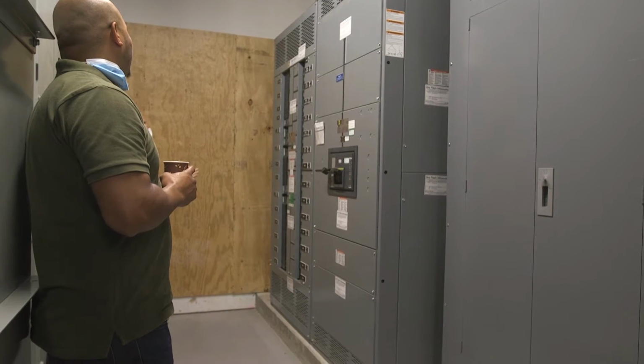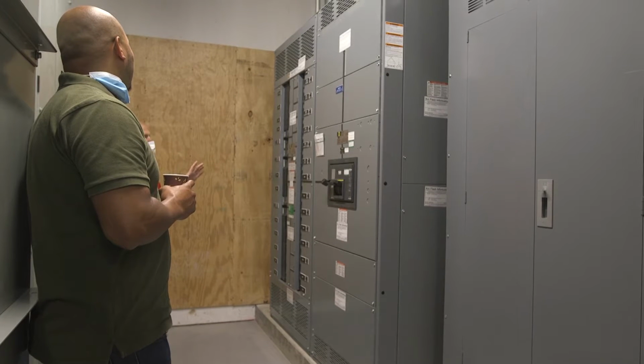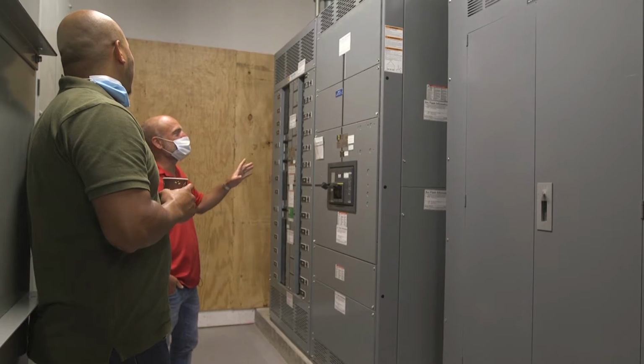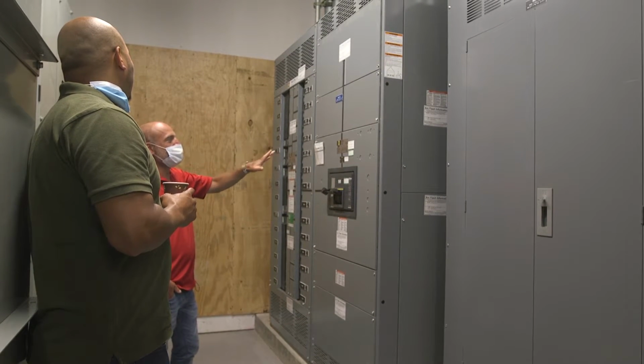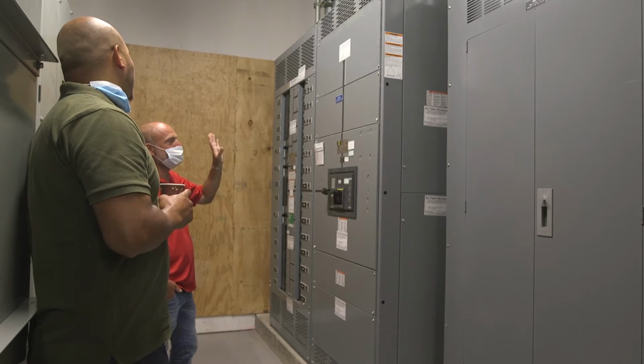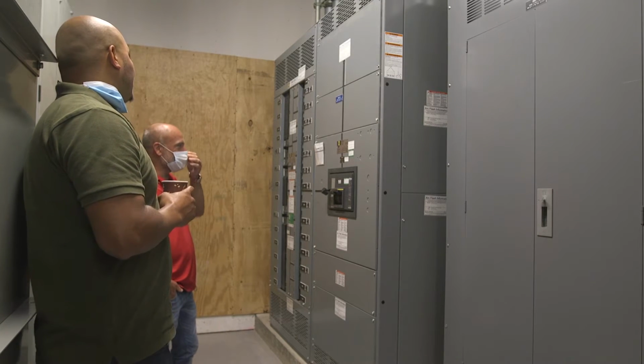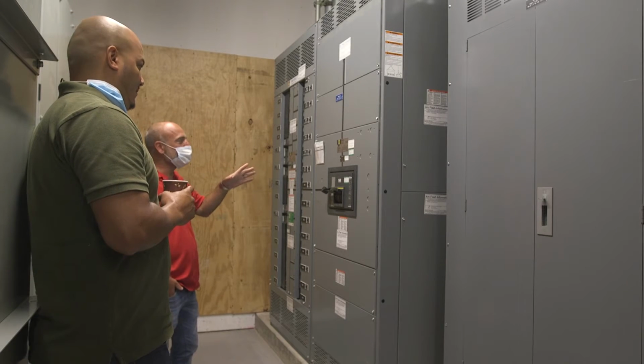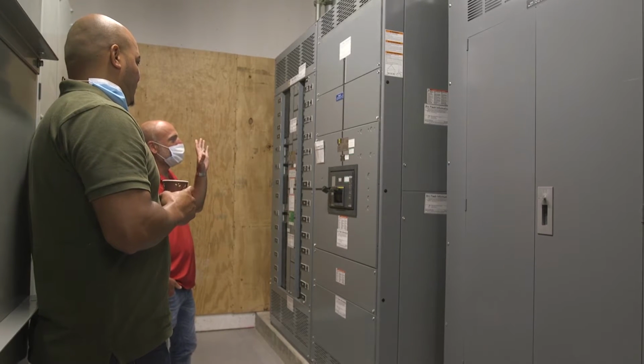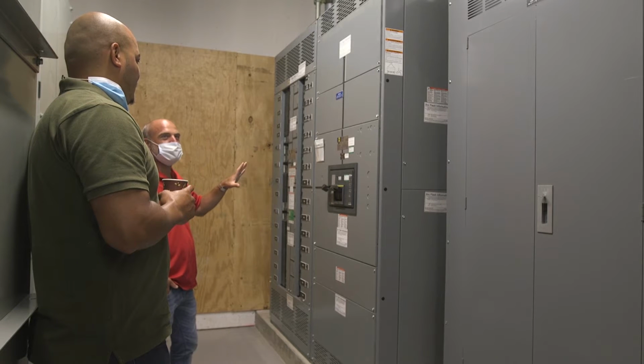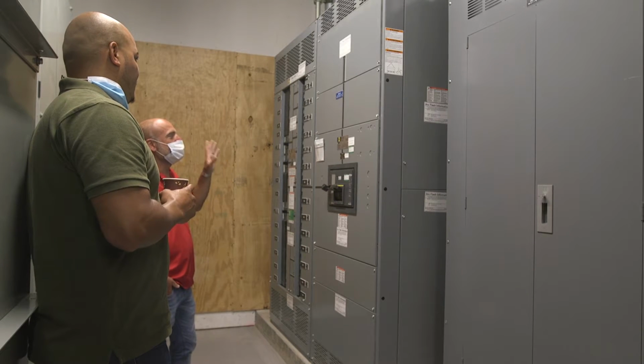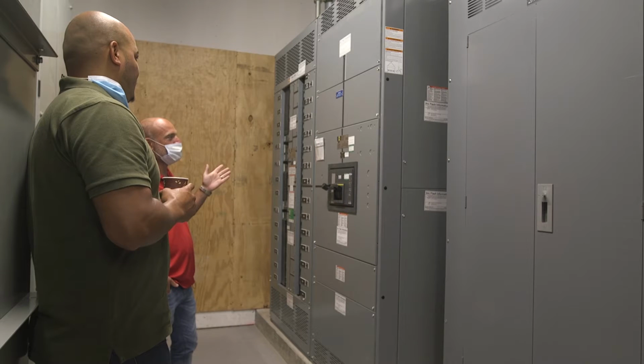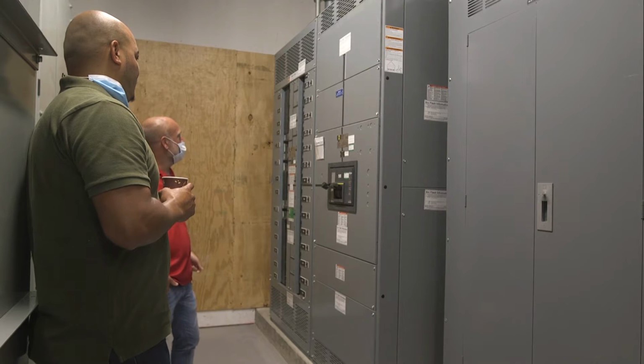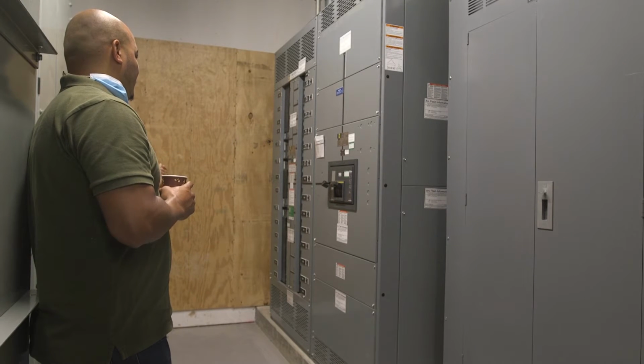QED2 switchboard. Some of the important characteristics are the nameplate, which is going to have all your information, your amperage, your voltage. Importantly, it's going to have your Square D build number, and that's if there's ever any kind of service information or anything that's needed for it. If you have to call Square D or call someone, that's the number that you would need. Basically, this is taking the main power and distributing it to all the other panels in the facility.